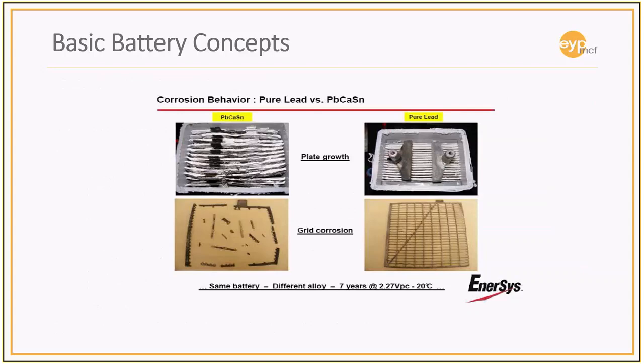As a battery degrades over time, if you could take it apart in the middle of its life, you'd see that these plates tend to start to disintegrate or corrode. What you see on the left-hand side is a fully corroded plate, whereas on the right-hand side it's almost a completely new plate. Over time, these plates will dissolve and you lose capacity within your systems.